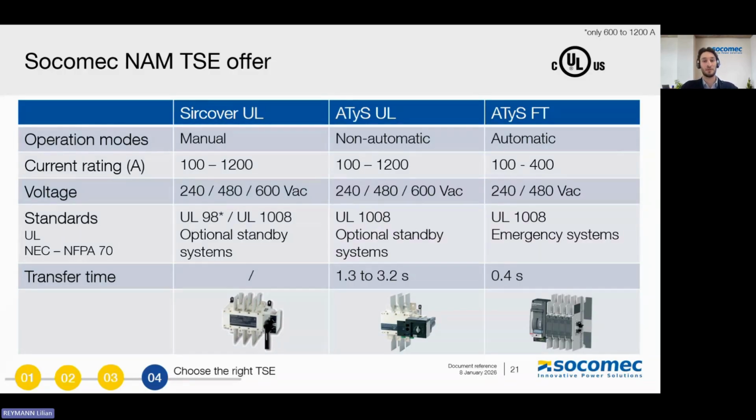If you would need emergency systems rated products or legally required system, you will need to have an ATyS FT, which transfer from a source 1 to source 2 in less than a second. And if you will need optional standby system, we will have the Sircover UL as manual transfer switch and the ATyS UL for non-automatic or remotely operated transfer switch, which occurs in 1.3 to 3.2 seconds.